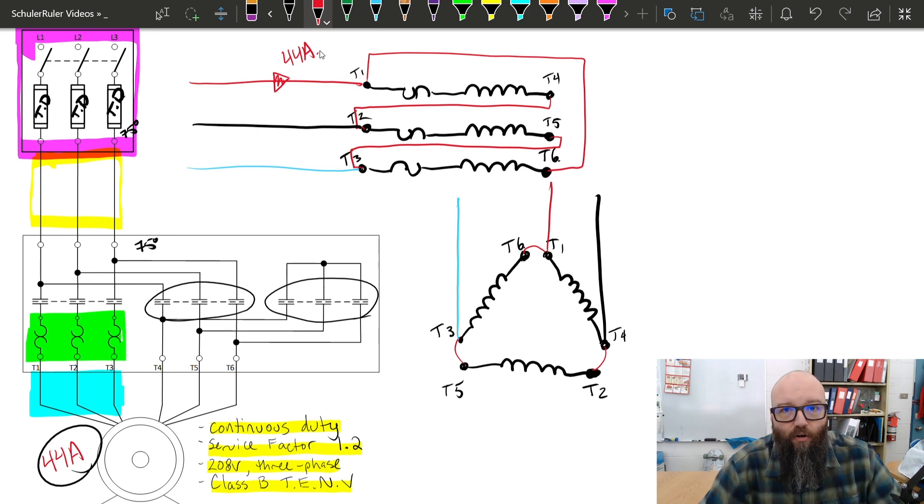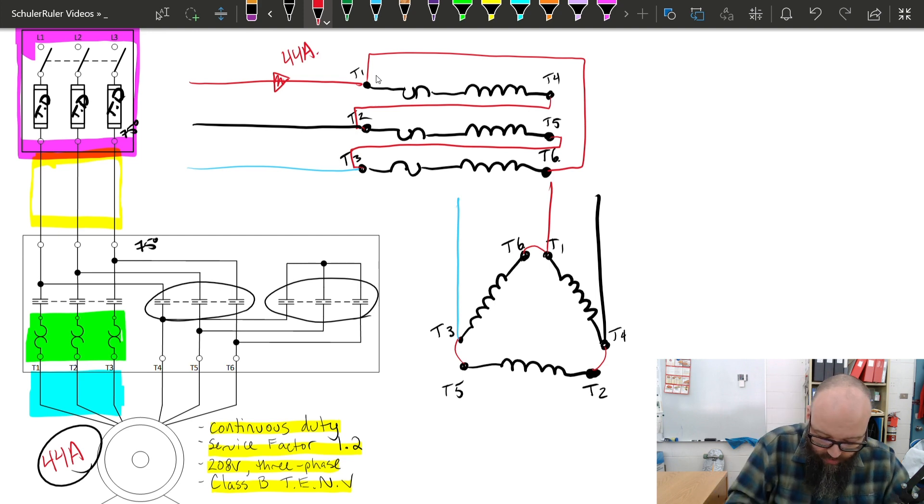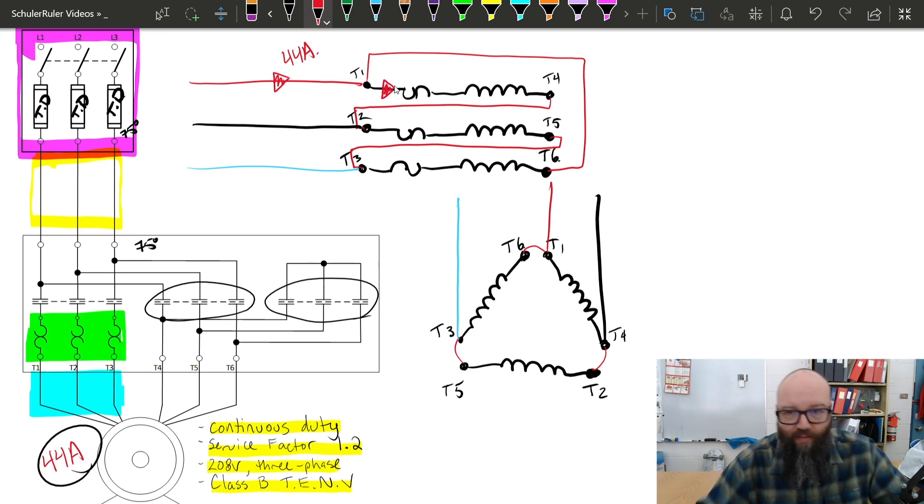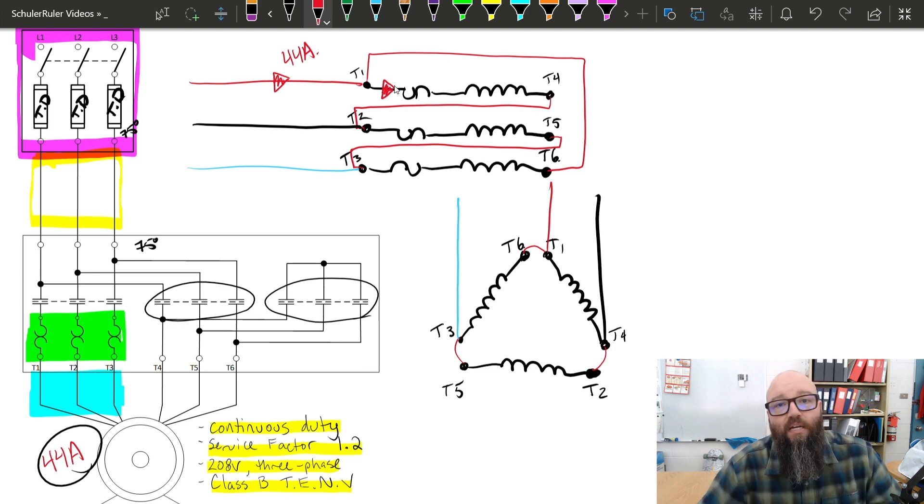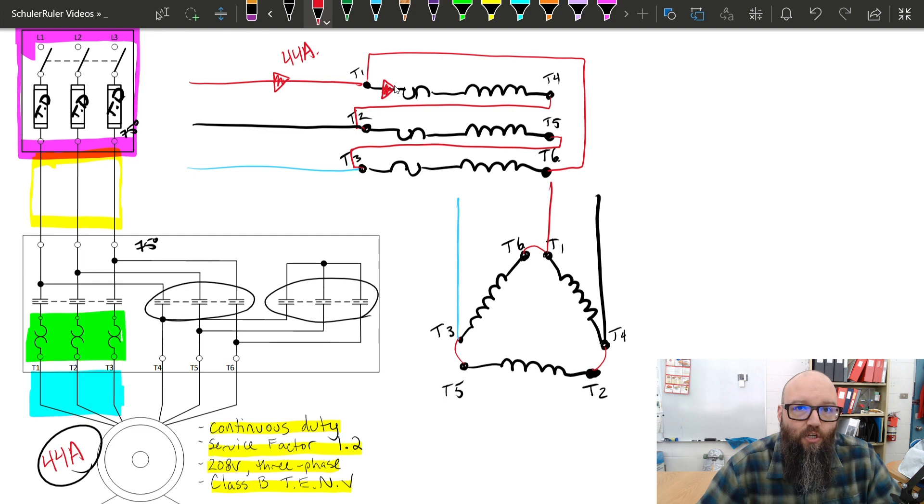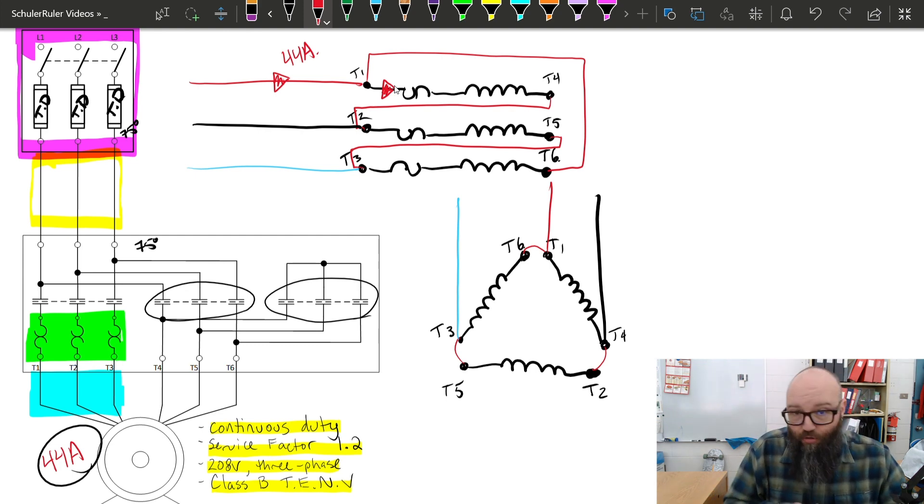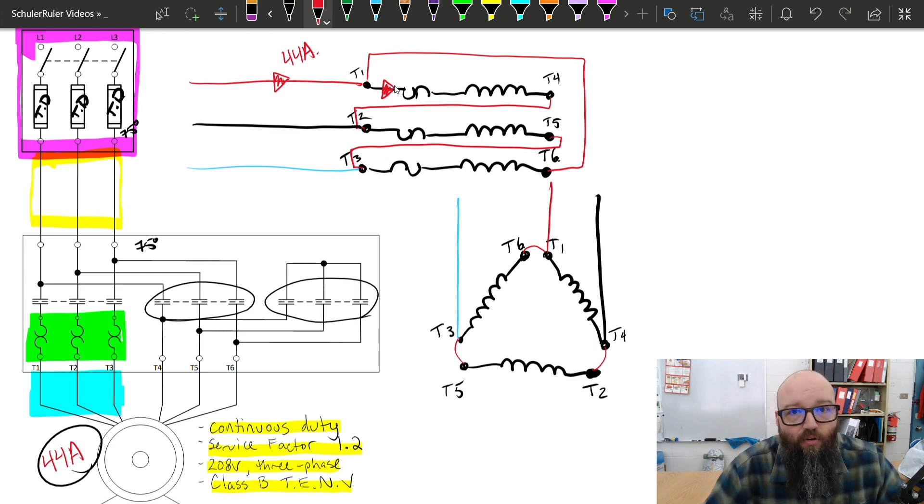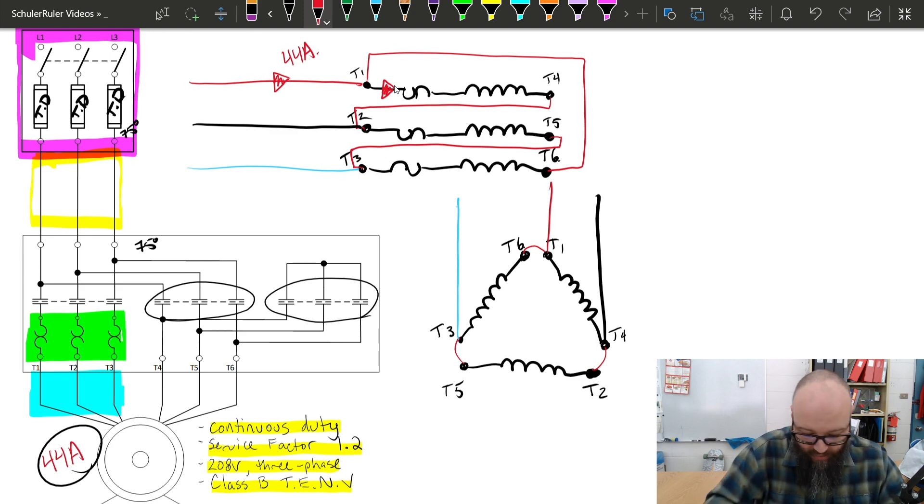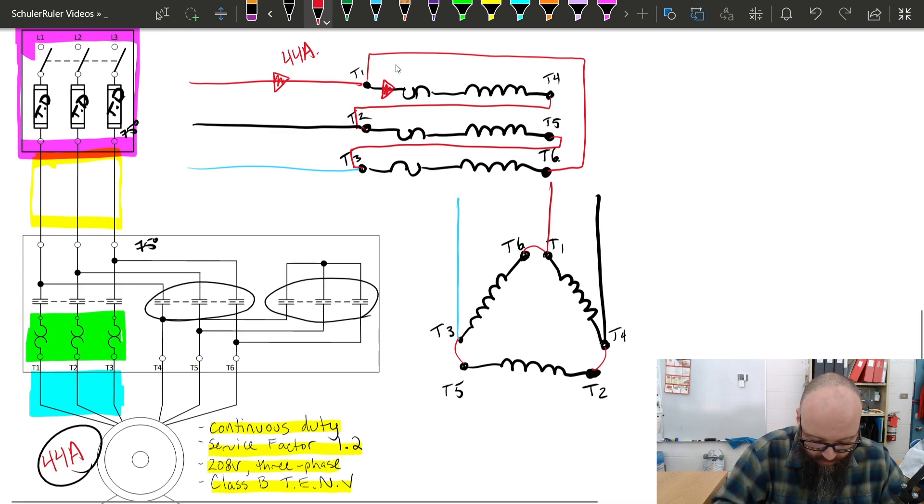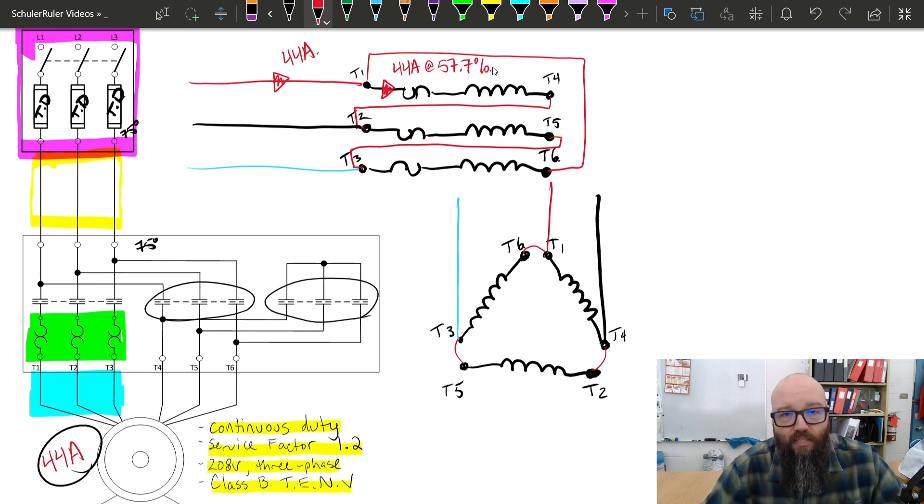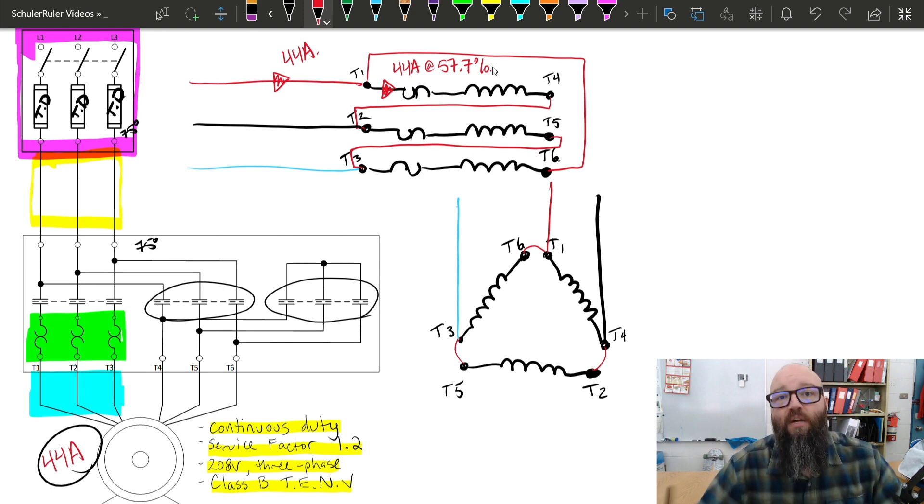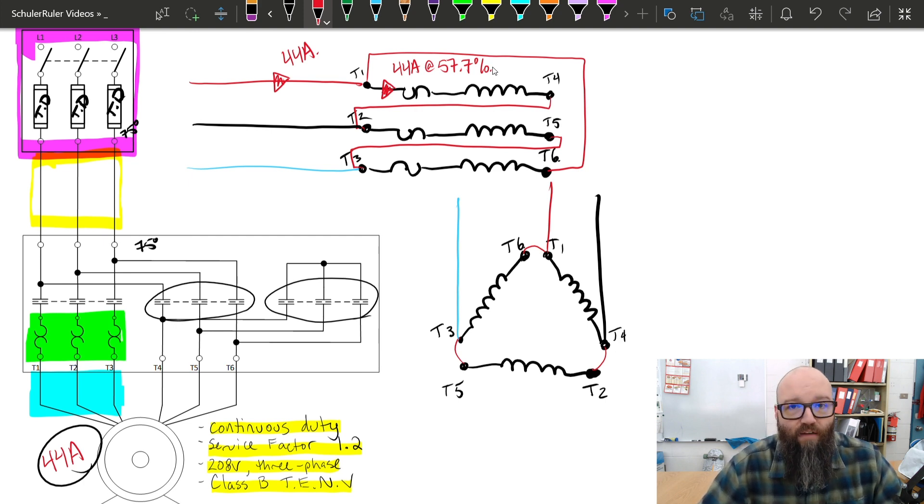What we're seeing coming into our circuit here, that FLA of 44 amps, that is my delta run current. But, if we pay attention, for example, at that T1 junction, I now have a division of that current. And what we know from that delta three phase theory is that phase current with respect to line current should be root three smaller. So, what I'm going to experience throughout that series connection of where my overload heater and my run winding is, or rather my motor winding, I'm going to see 44 amps at about 57.7%. The reason I'm using a percentage here is because when we go to reference the code book, there's a specific note about that. I know it's about root three smaller. It is exactly root three smaller than that 44 amps.